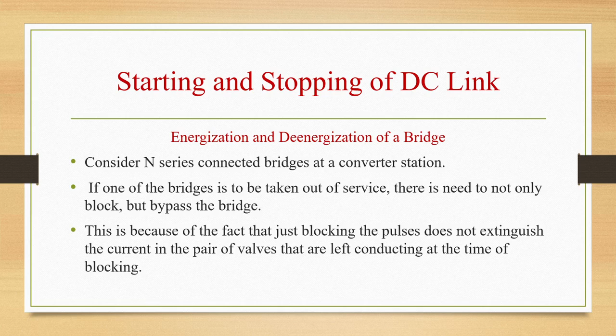So we are considering N series connected bridges at a converter station. If one of the bridges is taken out of service, there is a need to not only block but also bypass the bridge. Why are we bypassing the bridge? Because just blocking the pulses will not extinguish the current in the pair of valves that are left conducting at the time of blocking. When we block a path, the current should not pass through it, but that is not happening. That is why we bypass the bridge.